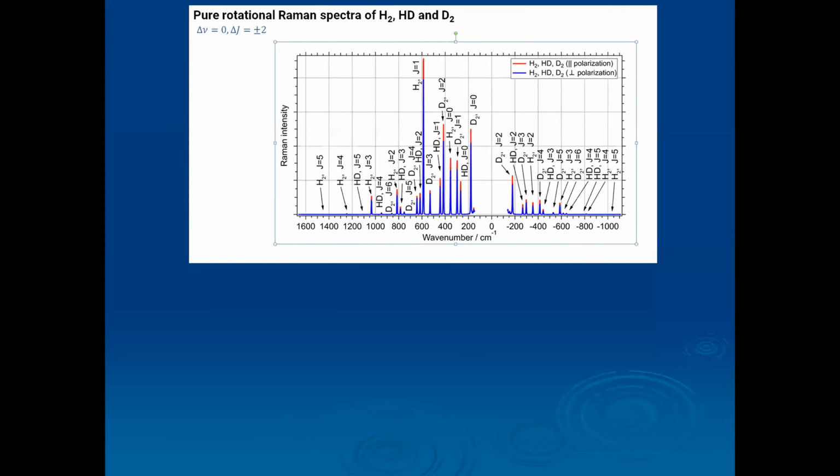And his idea was the following one. Let's take the simplest system we can actually calculate, H2. And this H2 has many rotational-vibrational lines. And these lines are located between 200 and 1200 wave numbers in the Stokes region. If I take the intensity of these lines from theory, calculated very accurately, and compare what his detector is counting, the number of photons that come at every pixel, you can design a correction in the spectrometer he has.